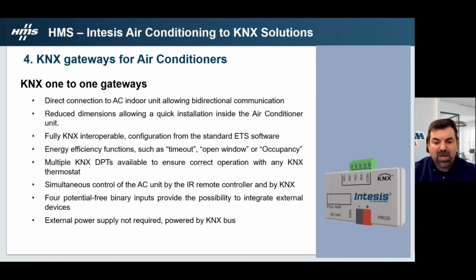Our KNX one-to-one interfaces provide 4 potential free binary inputs that give us the possibility to integrate external devices and no need to have external power supply. This is because the KNX one-to-one is powered directly by the KNX bus.